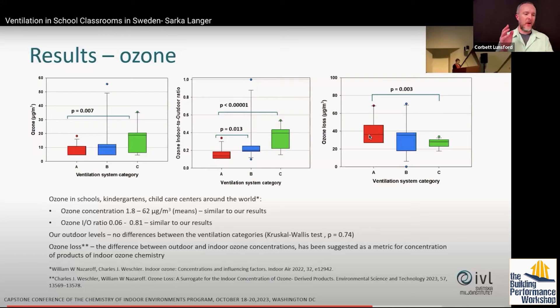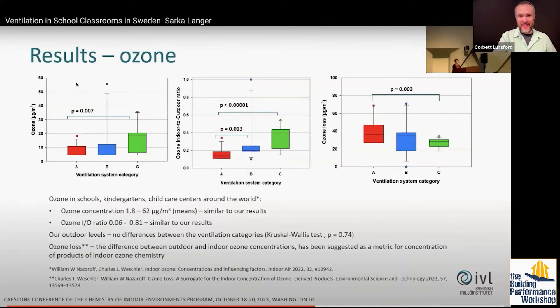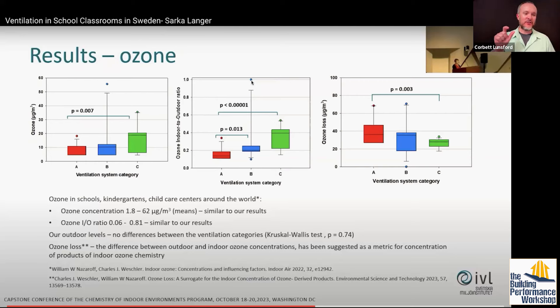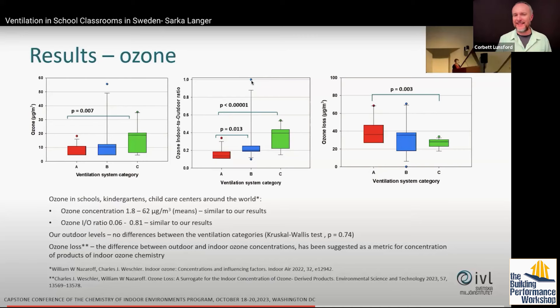Basically, ozone is like the TVOC conversation — maybe not the best single metric for measuring indoor air chemistry because there's a lot going on. There were also extreme outliers; one was caused by a teacher opening the window on a polluted day in a classroom that had an ERV running in constant airflow mode, supplementing it when something was happening outside. That's what caused that outlier.